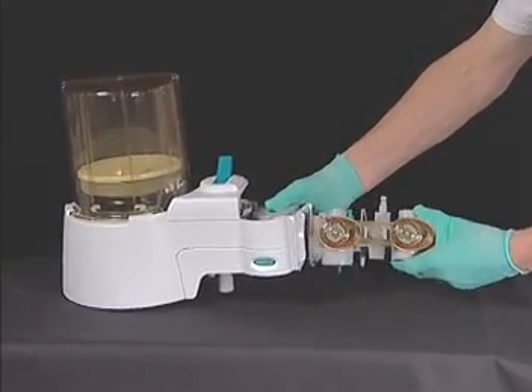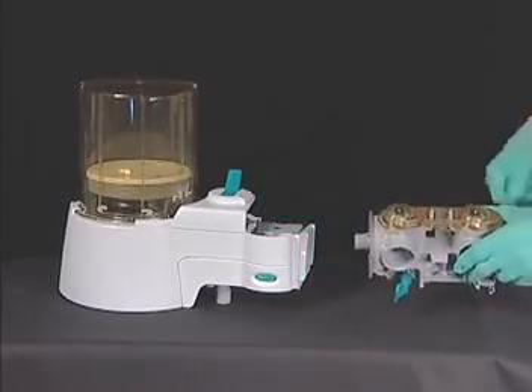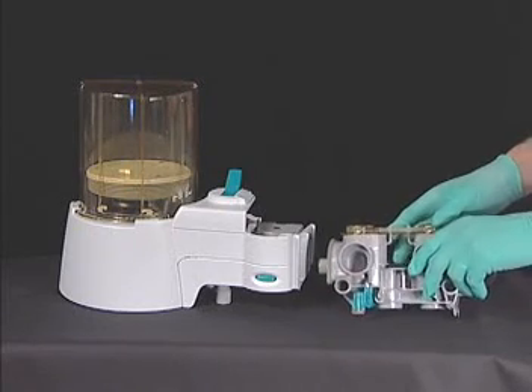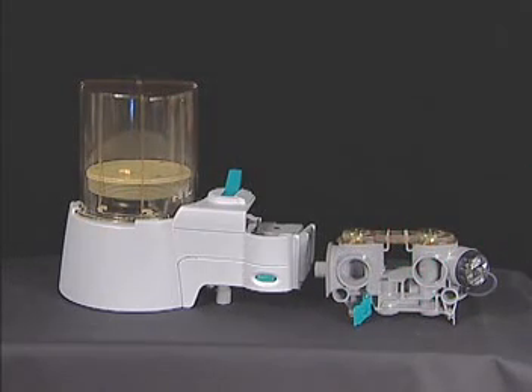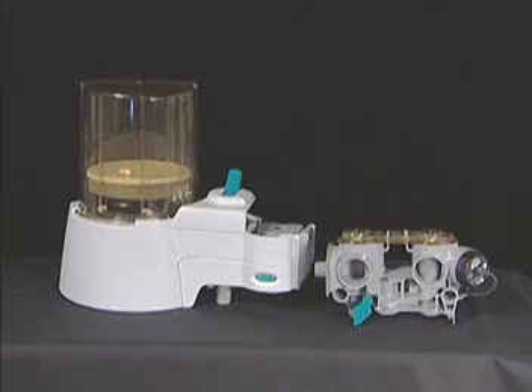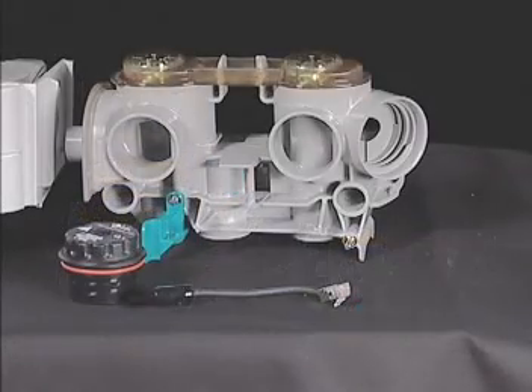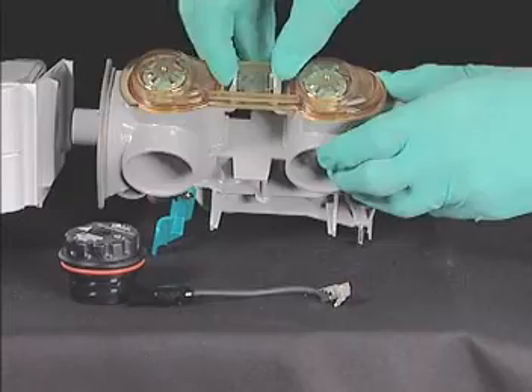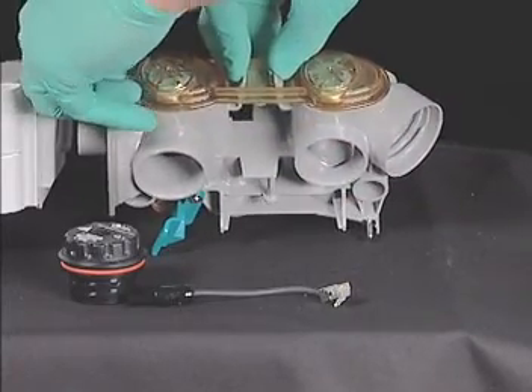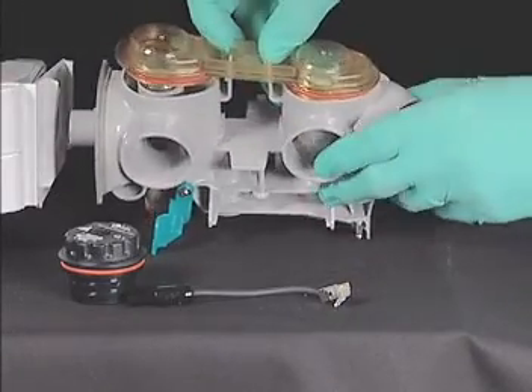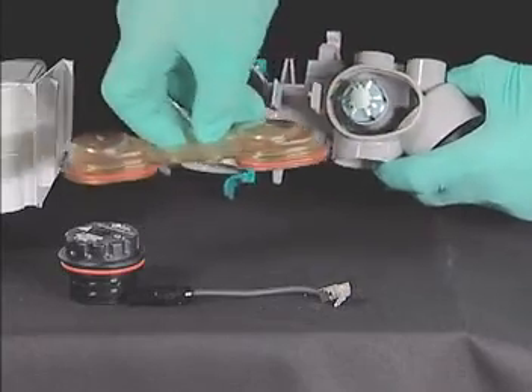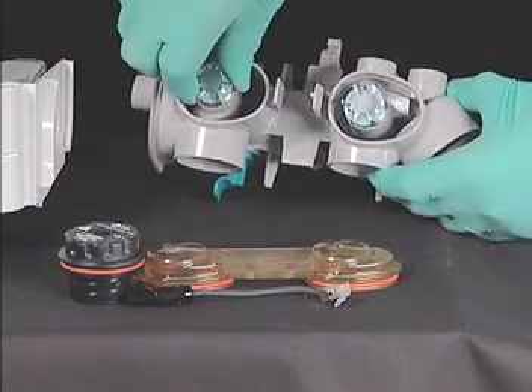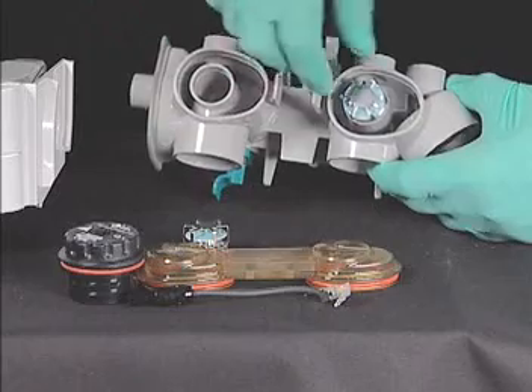Rotate the circuit module counterclockwise while holding the bellows base firmly. The bayonet-style connector is easily released, separating the ABS into two sections. If desired, the inspiratory and expiratory flow check valves can be removed and cleaned by squeezing the two tabs together and pulling up on the check valve cover. Reach in to remove the check valves.